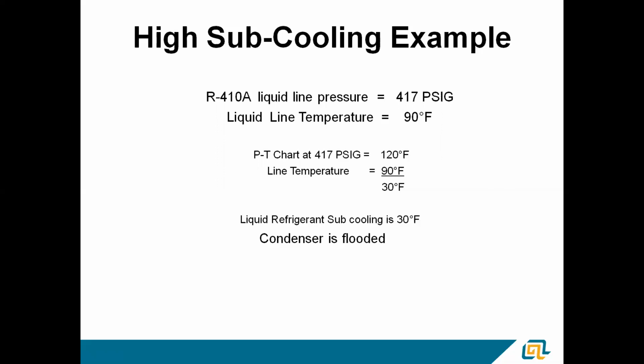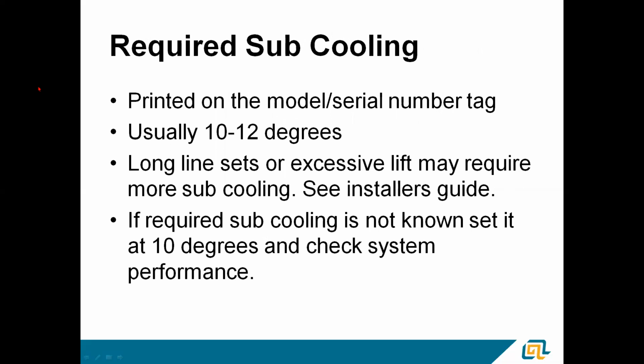That condenser is flooded. There's way too much refrigerant in that condenser. Either somebody's added a lot, or you could have a restriction, a bad TXV that's not open and not allowing that refrigerant to flow enough. The required subcooling is always printed on the model number, serial number tag of our Trane American Standard equipment. It's usually 10 to 12 degrees.